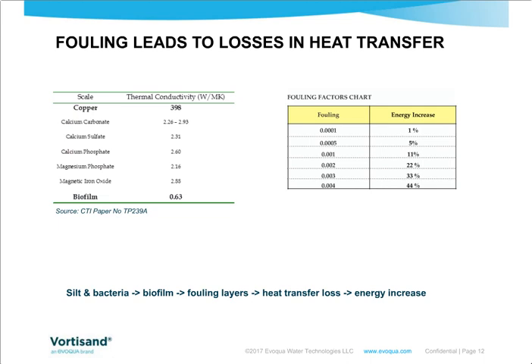Now, in your heat transfer applications, your heat exchangers, your cooling towers, your chiller loops, you're all using copper. Copper, you want to basically transfer heat. So you want to use a material that's very good in thermal conductivity. And if you compare copper's thermal conductivity to that of biofilm, you see a drastic reduction. That thermal conductivity, because of that biofilm layering, will reduce your heat transfer within your heat transfer surfaces, which will then, over time, lead to losses of energy.